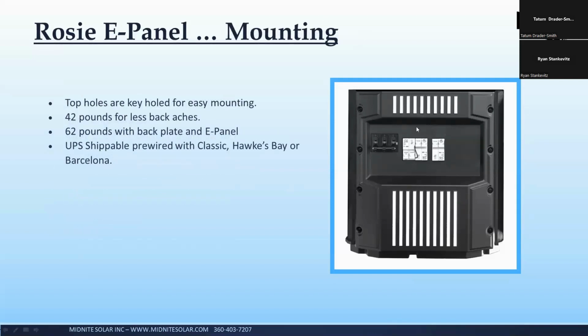The Rosie itself, so we're going back to system and weight and talking about the advantages of low frequency. The Rosie itself has keyholes on the top of it. So at 42 pounds, it's still pretty light, but when you're putting it on the wall, you can slide it down over the keyholes. So you can do the pre-wired in several ways. You could set the back plate right on your workbench. You could set the Rosie and the E-panel on there, bolt it all together, pick this thing up and put it on the wall, because completely assembled, ready to rock and roll is 62 pounds with the Rosie, the back plate, and the breaker box.